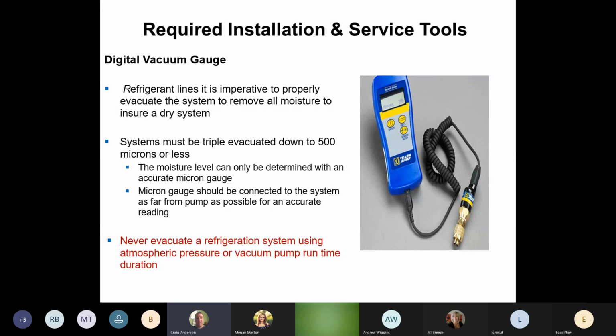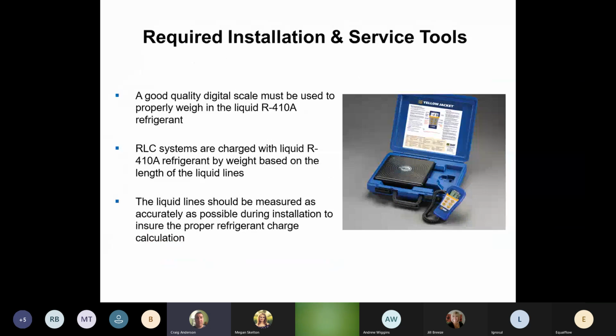Scales as well. Every service guy, every installation guy needs a scale in their truck. They do not have a scale in their truck. They are not properly charging a system. Most systems, and read the manual, everyone is a little different. Some are charged for 15 feet of line set, some are charged for 25 feet of line set. If it's over that length of line set that it's charged for, we need to add gas. The only proper way to add it is to weigh it in. If you're not weighing it in, you're not doing it proper.